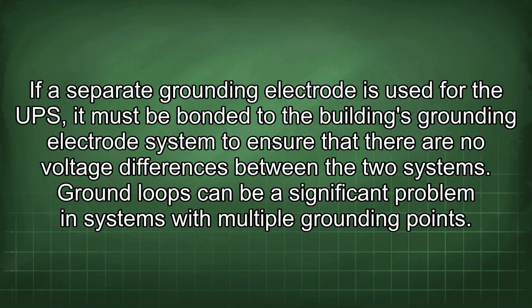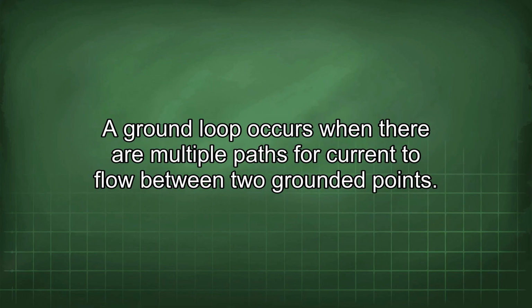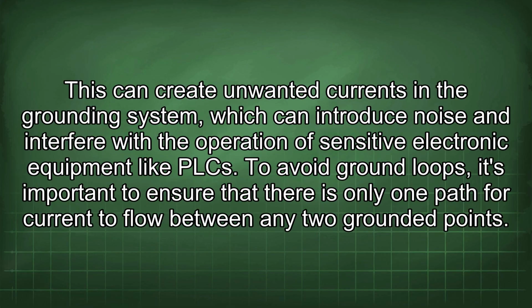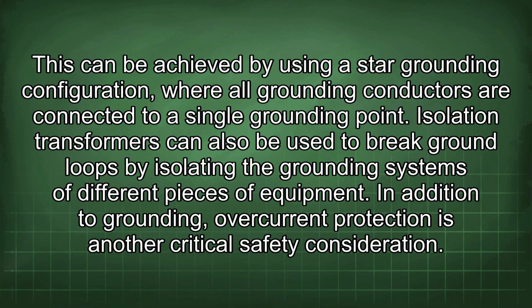Ground loops can be a significant problem in systems with multiple grounding points. A ground loop occurs when there are multiple paths for current to flow between two grounded points. This can create unwanted currents in the grounding system, which can introduce noise and interfere with the operation of sensitive electronic equipment like PLC. To avoid ground loops, it's important to ensure that there is only one path for current to flow between any two grounded points. This can be achieved by using a star grounding configuration where all grounding conductors are connected to a single grounding point. Isolation transformers can also be used to break ground loops by isolating the grounding systems of different pieces of equipment.